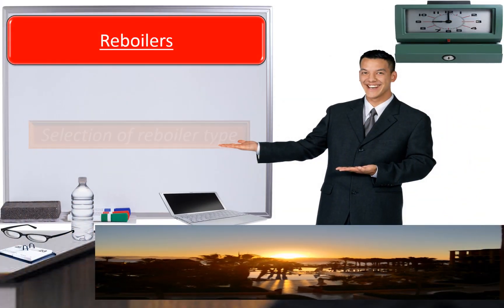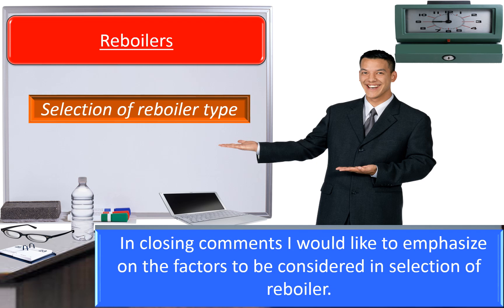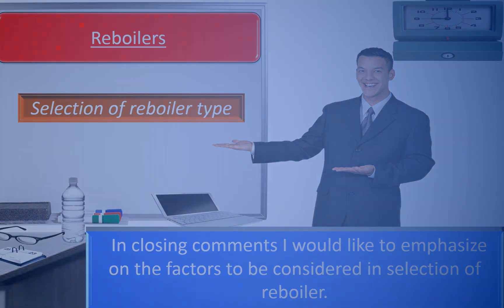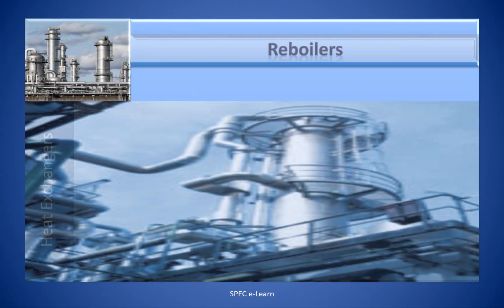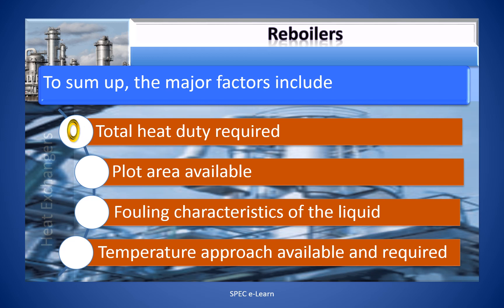Selection of Reboiler Type. In the two videos on reboilers, you have learnt the various types of reboilers. In the closing comments, I would like to emphasize the factors to be considered in the selection of a reboiler. To sum up, the major factors include: total heat duty required, plot area available, fouling characteristics of the liquid, and temperature approach available and required. All these four factors are to be considered with due importance in deciding the final choice.